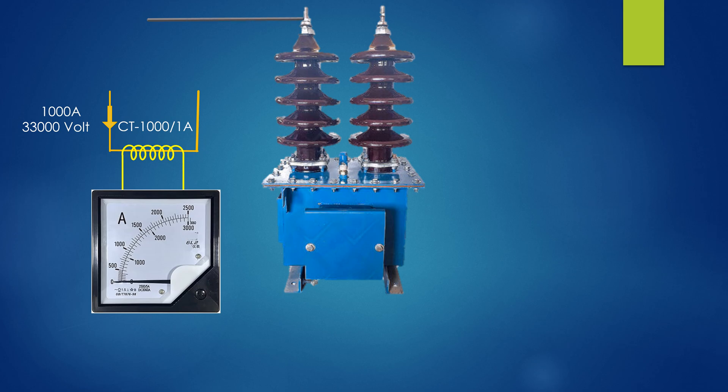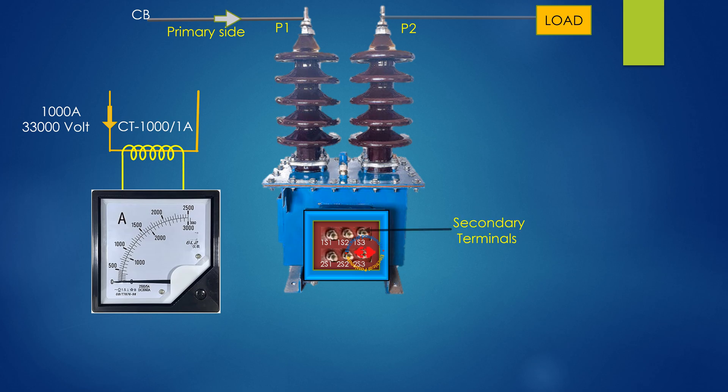Obviously, CT primary is connected with load in series. This is a picture of a 33kV CT having primary leads P1 and P2, and secondary has two cores with leads 1S1, 1S2, 1S3 and 2S1, 2S2 and 2S3. When a new CT is brought for installation, we have seen secondaries are shorted so that by any chance the secondary terminals are not left open circuited before termination. And if primary is connected with power circuit erroneously, no problem is occurred.